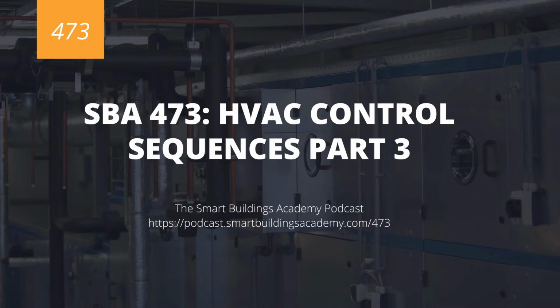So occupied operation will be determined via several different things: an occupancy schedule, forced occupancy override, push button override on the space sensor, an external scheduling device, etc. And what we typically will have is three modes as far as occupancy goes. We'll have unoccupied, occupied, and off. And there's an important reason we have off. If you are doing maintenance, you don't want to have it in unoccupied. You want to have it off. And that's really important because of unacknowledged alarms and all sorts of effects it may have on other sequences.